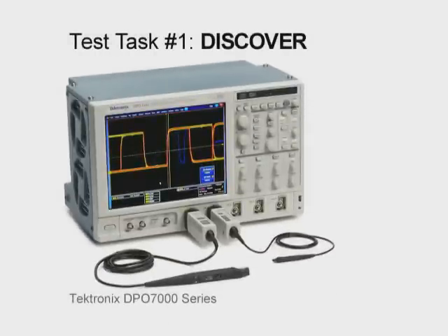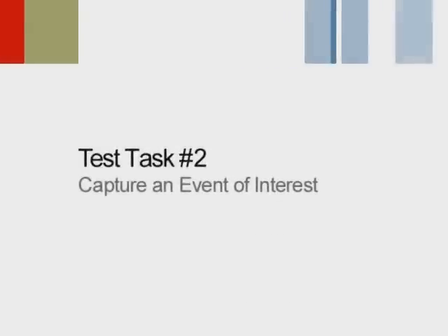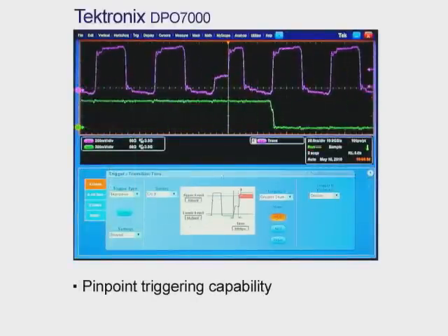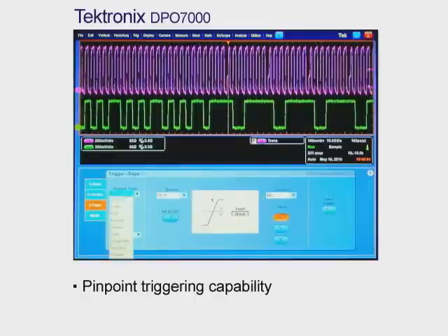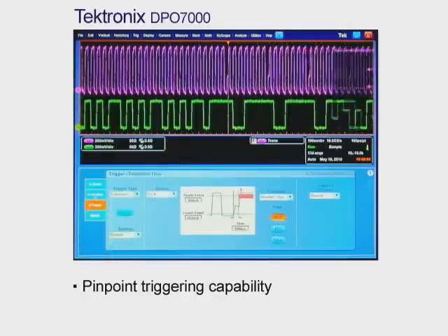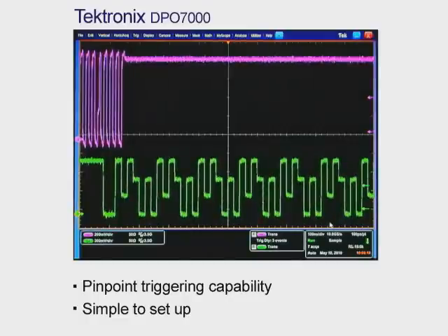After performing test task number one to discover the signal, finding a runt pulse is done much faster with the Tektronix DPO7000 than with competing instruments. Next, let's try to capture an important event of interest. Here we see how quickly the Tektronix DPO7000 does just that. With its pinpoint triggering capability, we can capture the runt and evaluate the transition time associated with the clock signal in a couple of simple setups using the AB trigger functionality of pinpoint triggering.